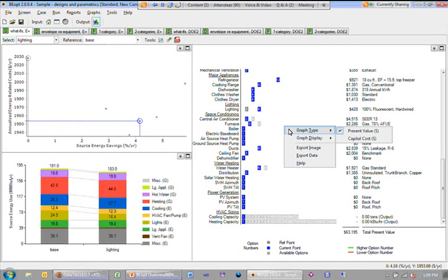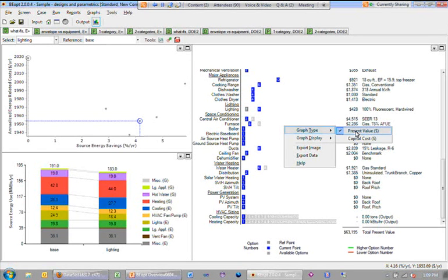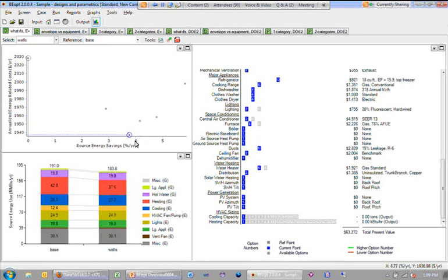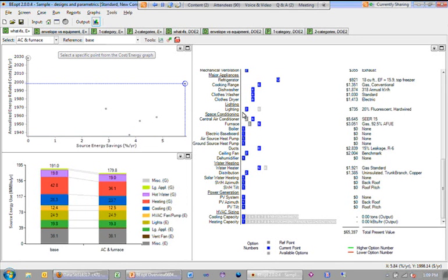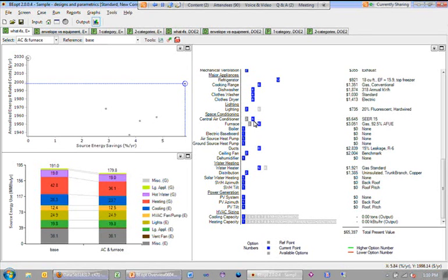If you right-click on this graph, you can look at the information in terms of either present value dollars or capital cost. Present value dollars would be your capital cost plus any replacement costs out in the future brought back to the present. If you've got a technology, here's AC and furnace design. You can see their improvements. Because these are two technologies that last for, we could look at how long they last for 15 or 20 years, let's say, and the analysis period is currently 30 years, there's going to be a replacement in the years 15 or 20 for these technologies and the replacement costs associated with that.